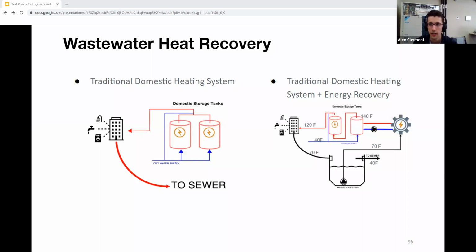Then that water gets used by the occupant and goes down the drain to the sewer system. Now, the sewer is not just composed of hot water, as it's mixed with cold water used for toilets and faucets, but the resulting water leaving the building going to the sewer, it depends a little bit on the building profile, is somewhere between 65 and 70 degrees Fahrenheit.